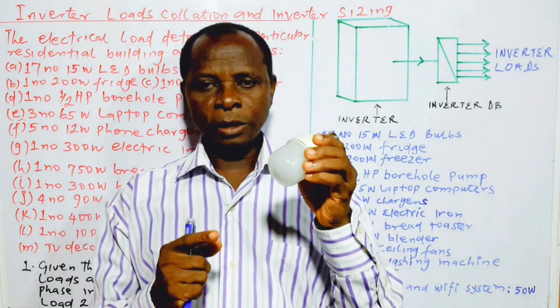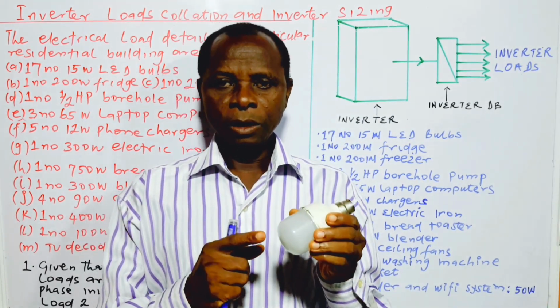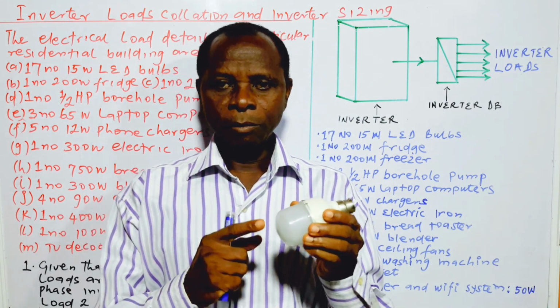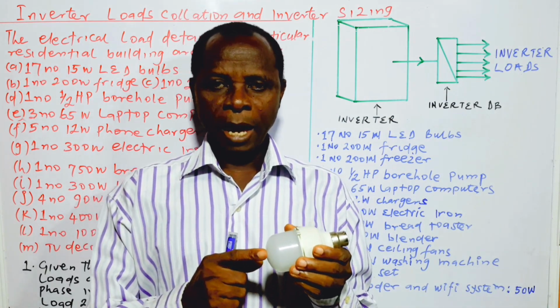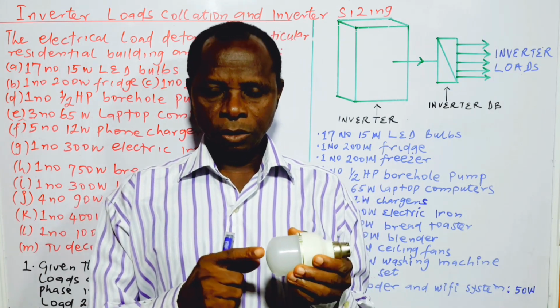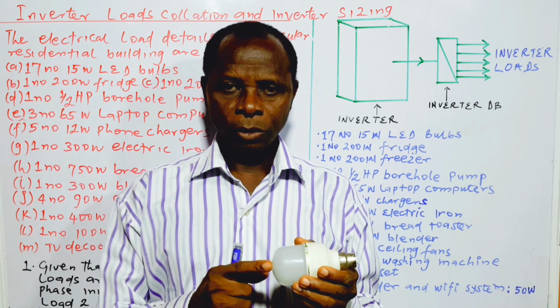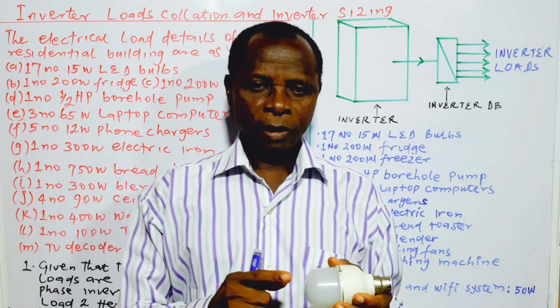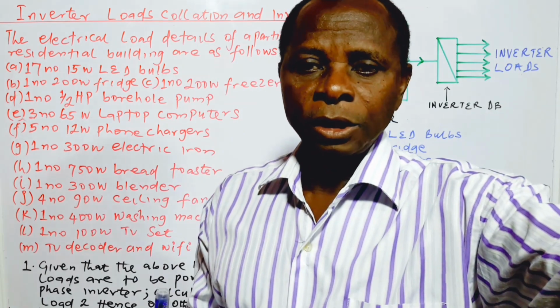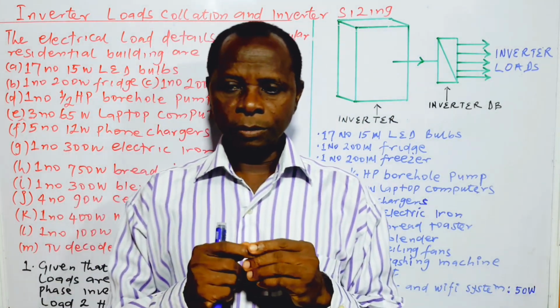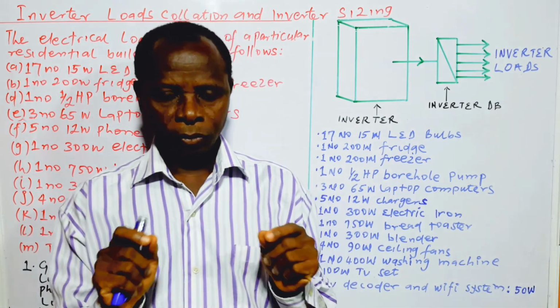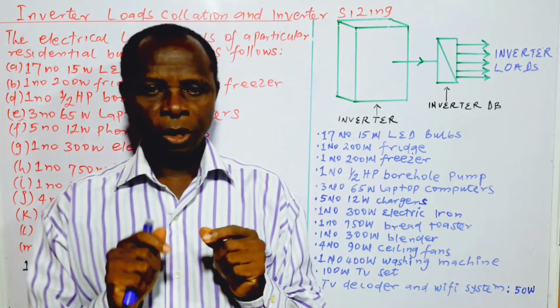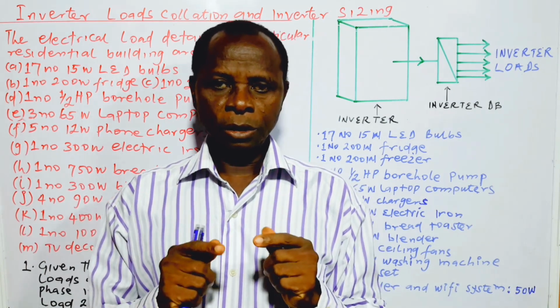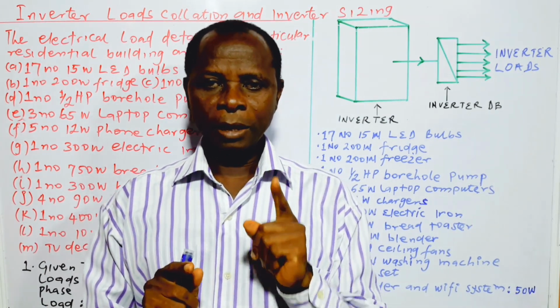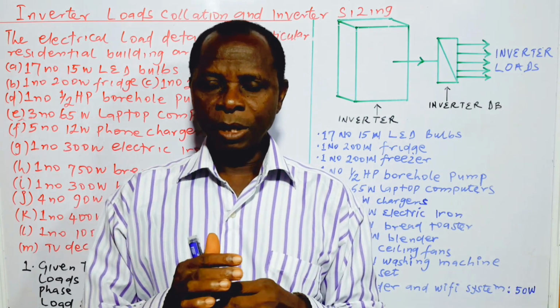Any rating that is given in VA will be converted to watts by multiplying it by 0.8. That 0.8 is the power factor. So that is very clear. However, in a situation where the power rating is not written at all, then the power rating of that particular device could be determined by making use of a clamp meter.